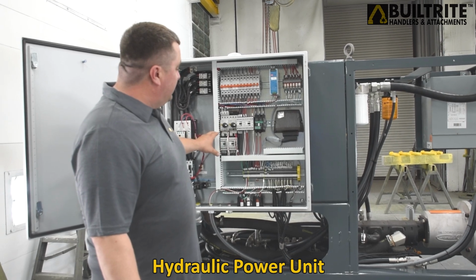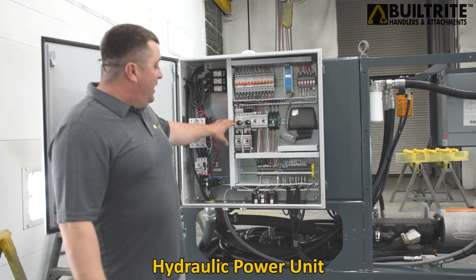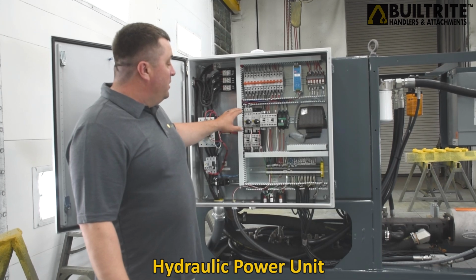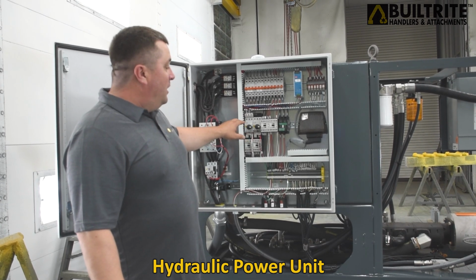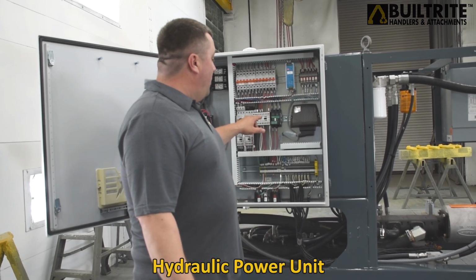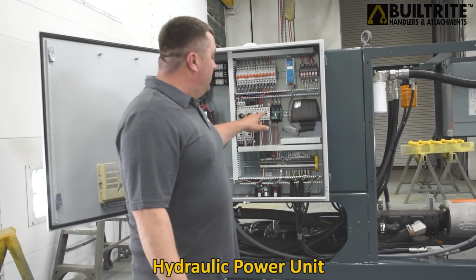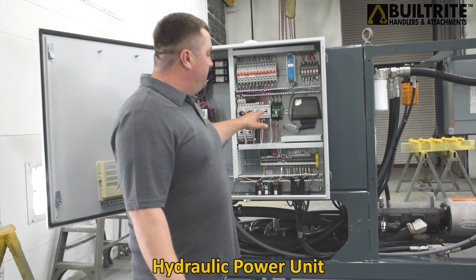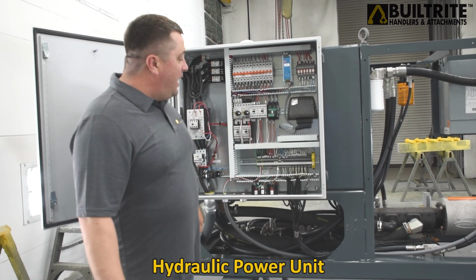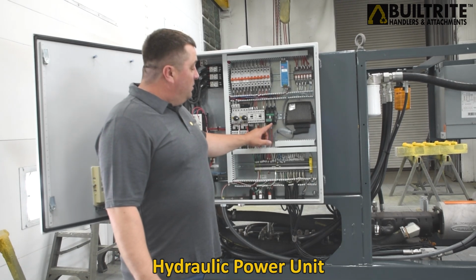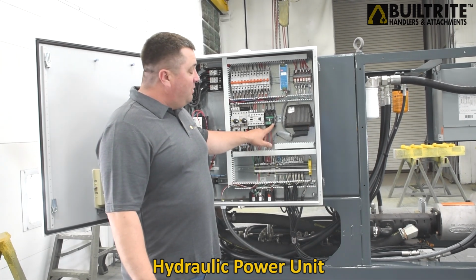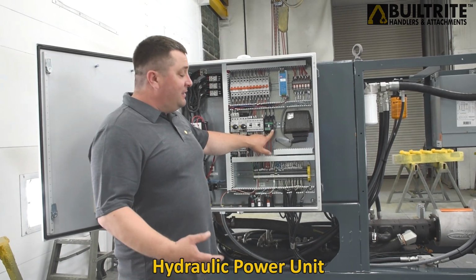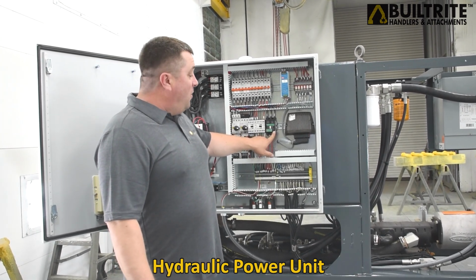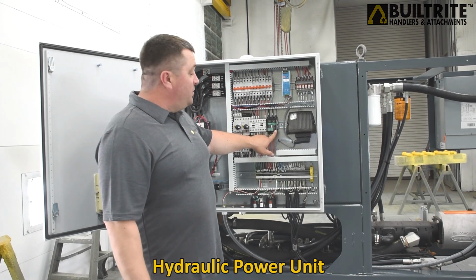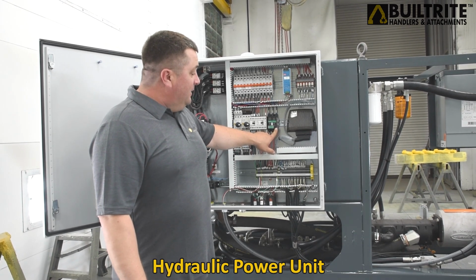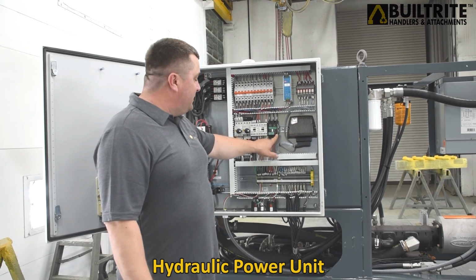Then moving down to the next section, we have the motor protection and motor starter for the cooler and the AC motor, along with contactors for the low oil and the tank heater itself. Right next to that, we have a phase monitor, which is indicated with a green light when all of your phases are correct. This is good for initial startup, or if you have a power surge or storm or something at your facility. This will indicate that your phases are correct.